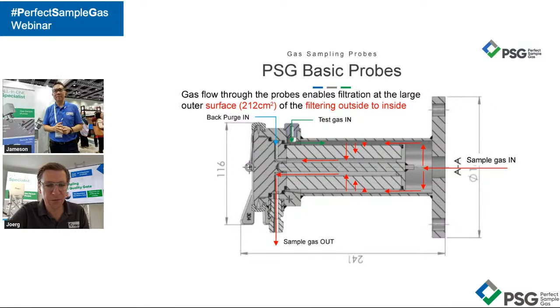Anything from you to this, James? Yeah, I fully agree that it is important that, whether it's in US EPA or in the European EN 14181, the calibration gas has to be entered into the very first equipment, starting from the sample probe. In this equipment I'm referring to the sample filter, meaning that the calibration gas has to go through and simulate the sample going through our filter element, then go downstream all the way to the gas analyzer.